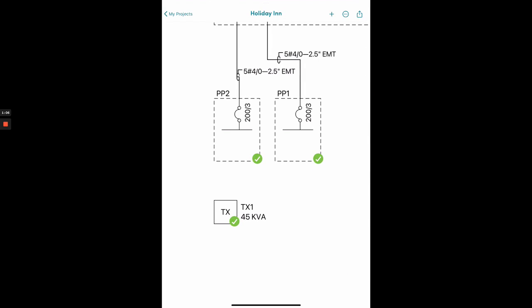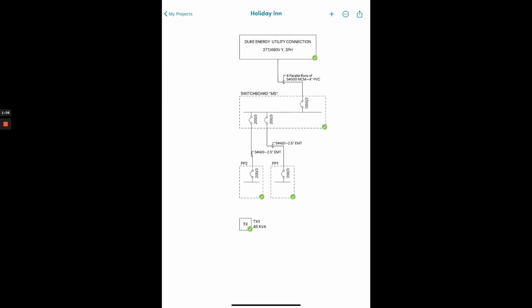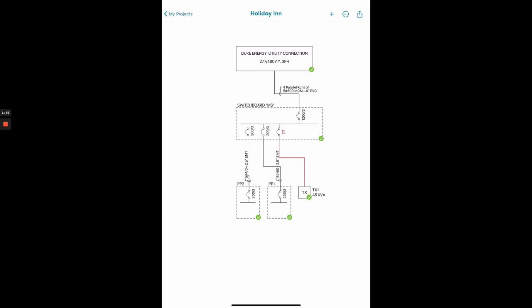Again, we haven't made any connections yet, so we don't know where it's connected, so we need to tell it. So we're going to hit the context menu, hit connect. It's going to bring up our upstream and downstream nodes for that transformer. We're going to tap on the transformer. Now we could connect this on PP1 or PP2, but we're going to add a breaker inside of switchboard MS and connect it there. So we look at switchboard MS downstream. On the bottom of switchboard MS, we can tap the node there at the plus breaker, and it's going to go ahead and draw a raceway for us there to transformer TX1.